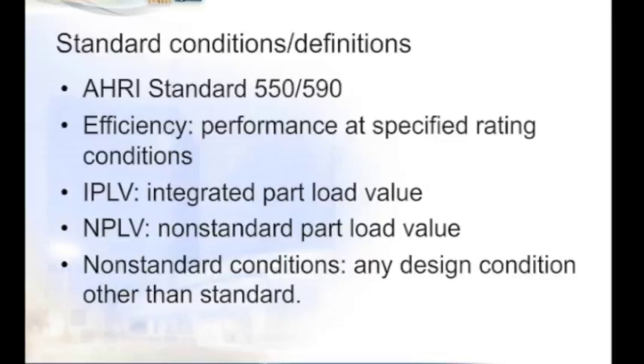Not for the system, but for the equipment. The NPLV, or non-standard part load value, is a single number part load efficiency figure of merit calculated and referenced to conditions other than the integrated part load values for units that are not designed to operate at AHRI standard conditions. And non-standard, obviously, is any condition that is not standard from either a temperature standpoint or water entering or leaving. So in selecting equipment and entering data into a schedule and project documents, it's necessary to know which values to schedule and indicate if they're going to be at non-standard or standard conditions.